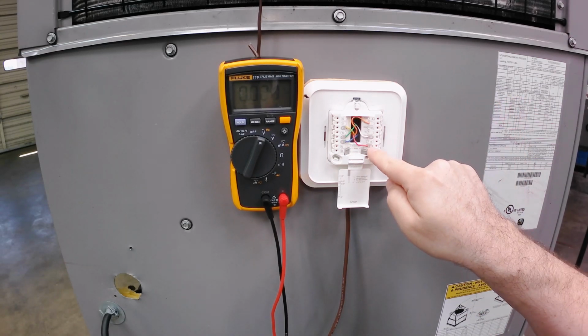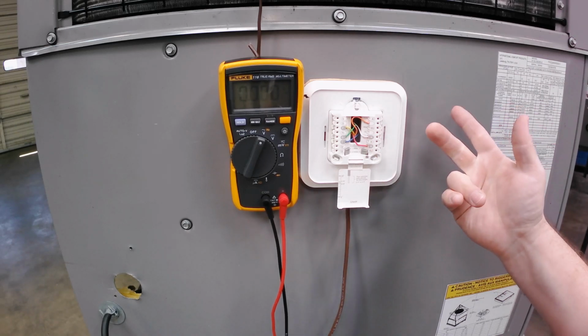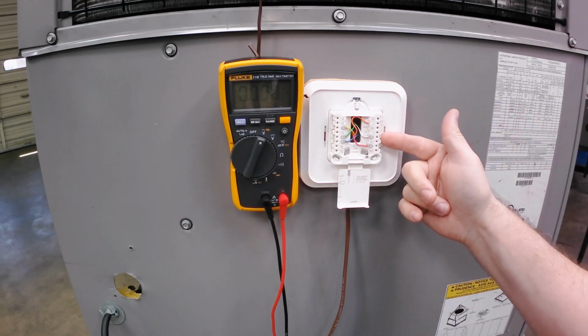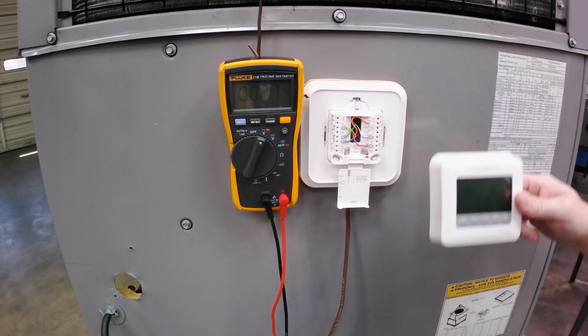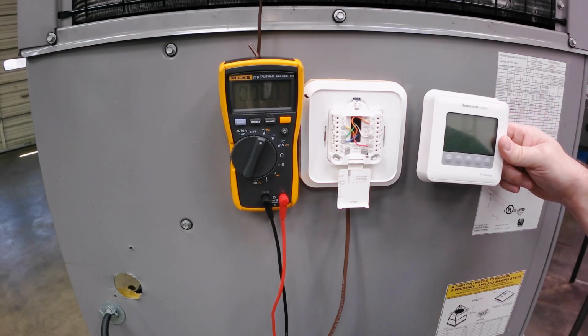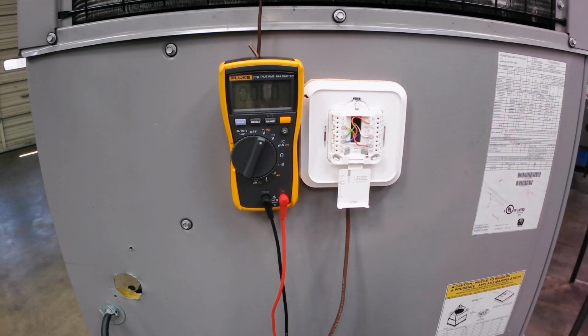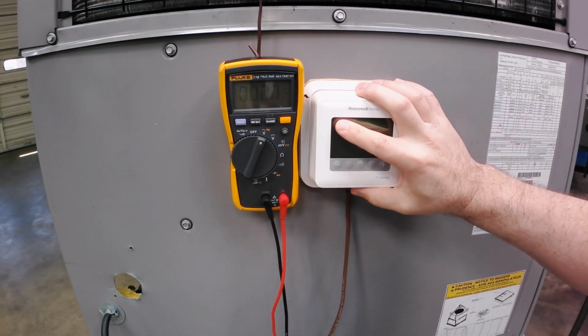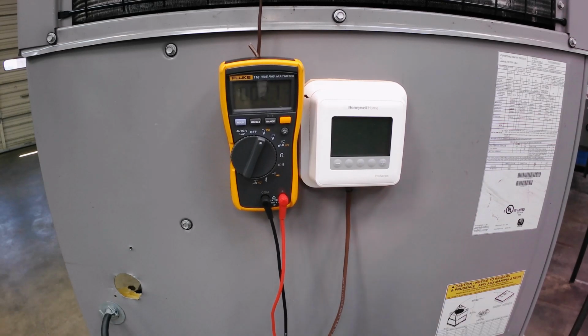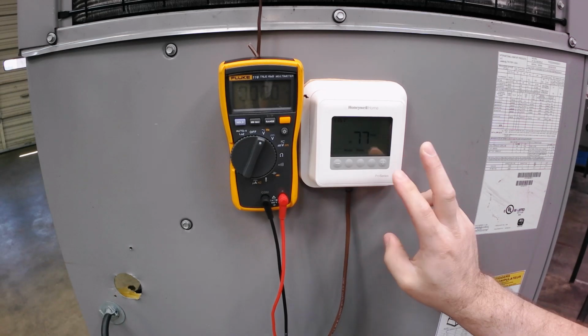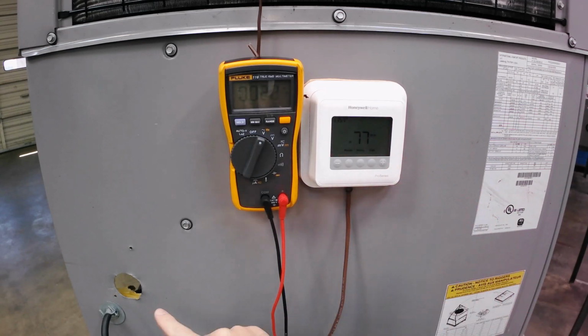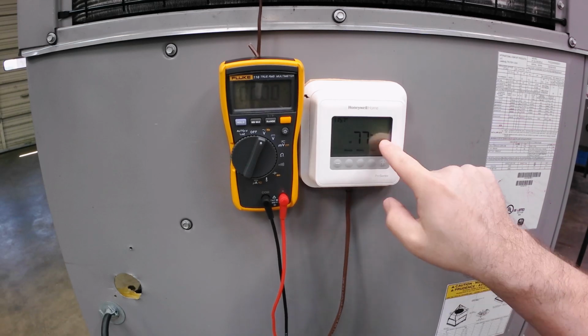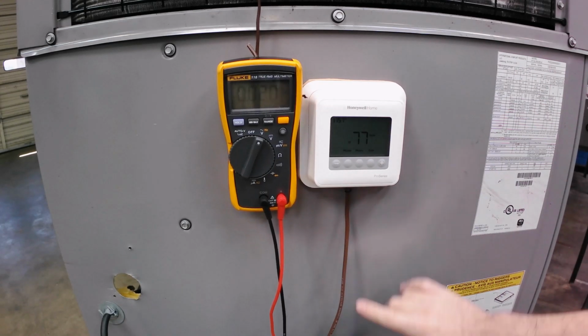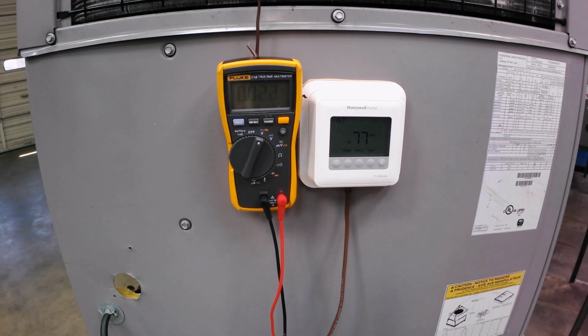So what's the difference in R and R? It should be 0 if we could check that, but because we remove the switches, now we're checking one side of power across a switch, and that's where guys get confused. Okay, so let me turn this back on. We're going to let the thermostat come back up, and like I said, for me, check power here at the thermostat. The next thing I would do is go to the other end, and you can see we've got our fan on in the on position here. The system itself is off, so we would go to the other end of the wire.